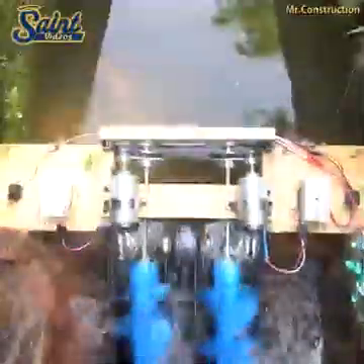Single screws can work on heads up to eight meters, but above this, multiple screws are generally used. In many cases, for heads above eight meters, there may be more appropriate turbines available with much smaller footprints.